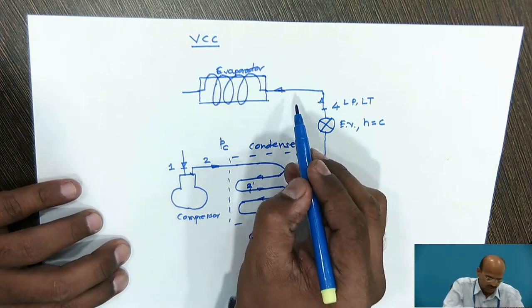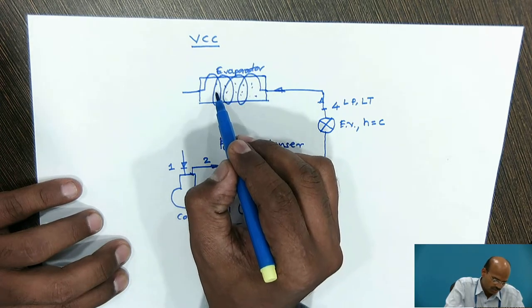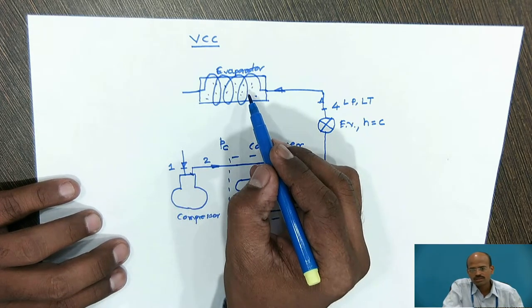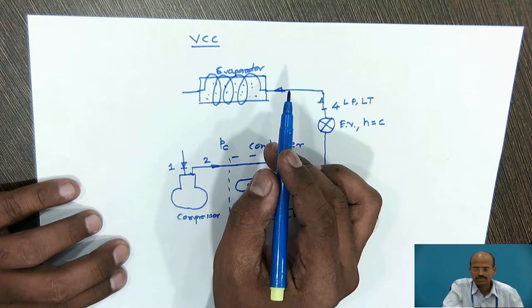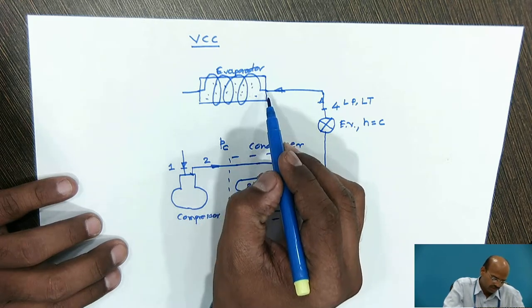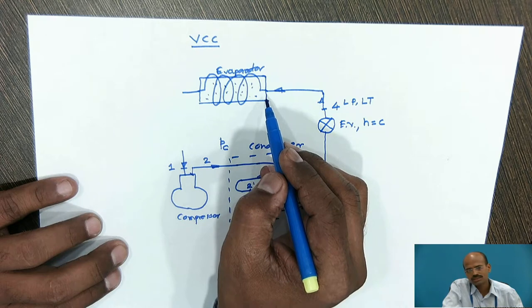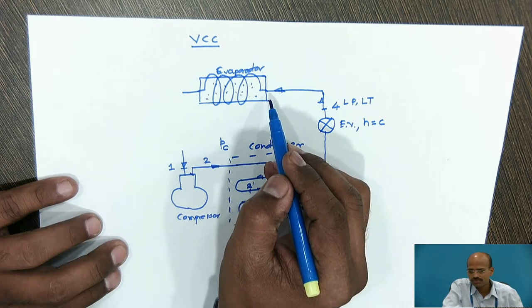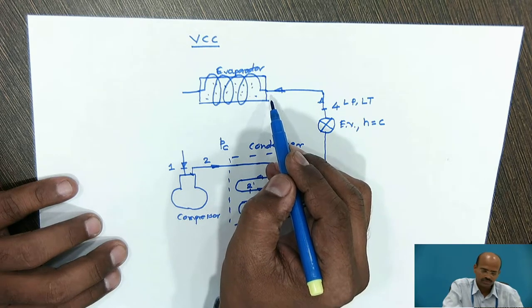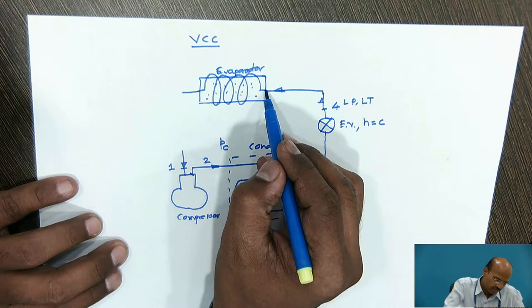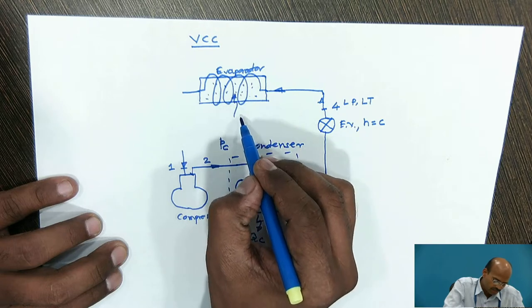When this liquid refrigerant starts flowing through the evaporator, it absorbs heat from the product to be cooled, which is kept in the evaporator. For a domestic refrigerator, we call this evaporator the freezer — where we keep ice creams or water for freezing. The heat absorbed by the liquid refrigerant involves a change in phase, so the type of heat is latent heat. This large amount of heat absorbed by the low pressure, low temperature liquid refrigerant from the stored product is the refrigerating effect, denoted by QR.